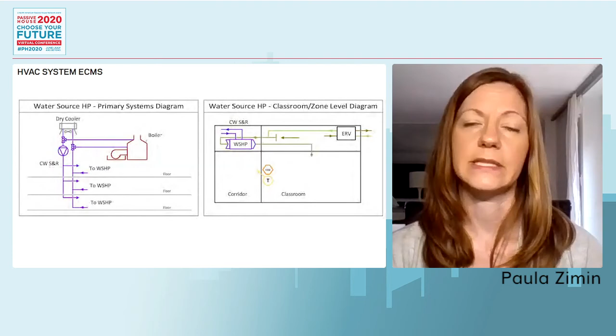The challenge with that ventilation strategy is where your exterior air comes from. And there are definitely several areas of New York City where you do not want to pull fresh air from the street side. So there's going to be limitations to how often that strategy can be implemented. But certainly a room-by-room ventilation strategy will reduce total fan power, and we noted that, but we decided that for this particular case study, it wasn't a solution that would work.